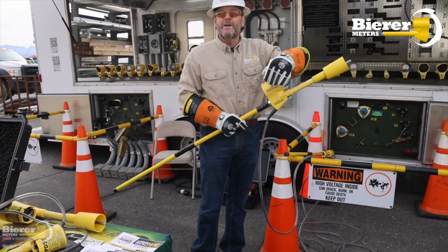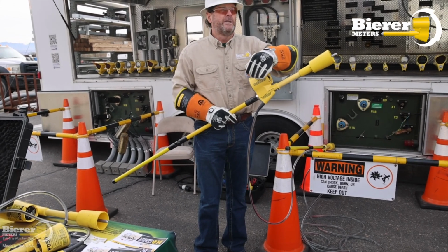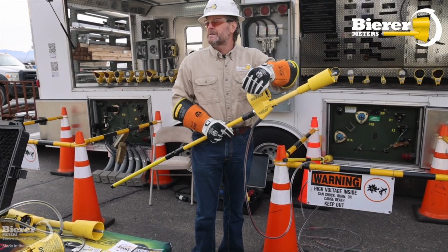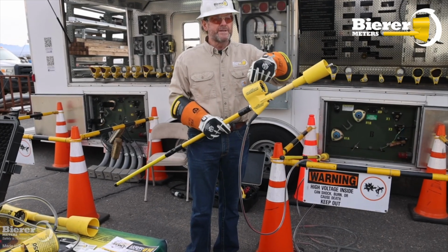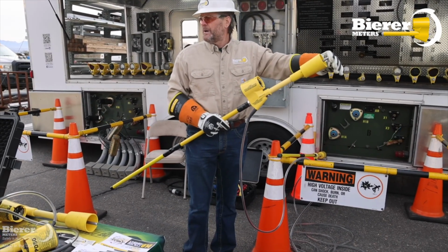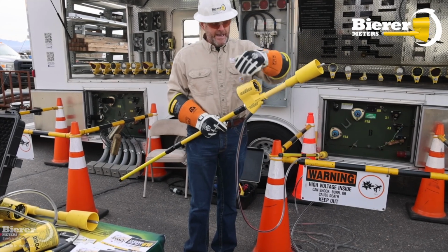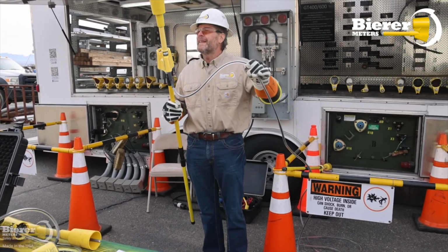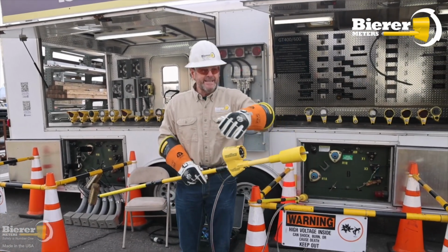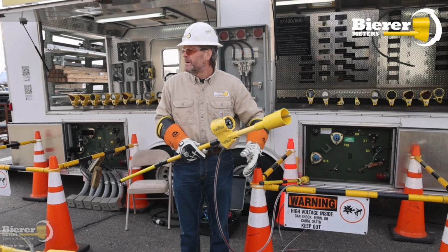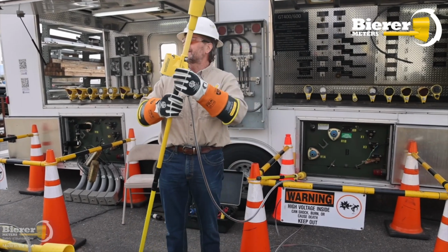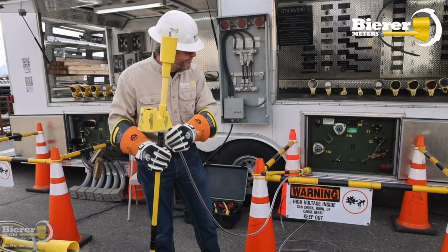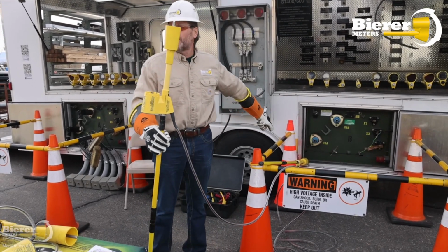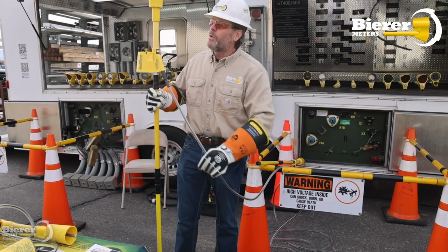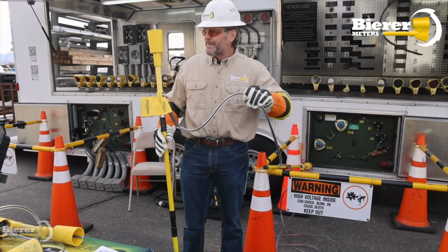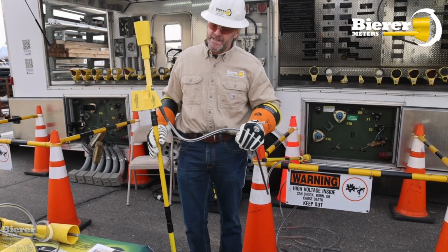There was another hot bus right next to the meter head. Primary power right next to the meter head. What happened was, you know how the tools work. You know that this tool is energized with this power, and they got a primary power here in direct relation to the ground plane without any resistors protecting that air dielectric. They didn't know. And what happened is that cord exploded at the meter head, that power that shot down to the secondary probe, exploded that cord at the secondary probe, and that cord was all black and charbroiled and in pieces.